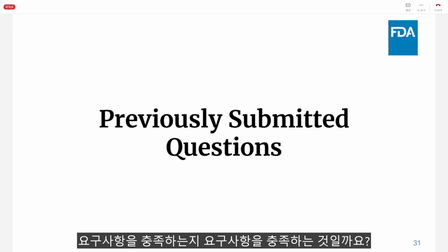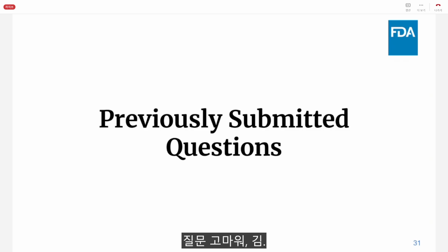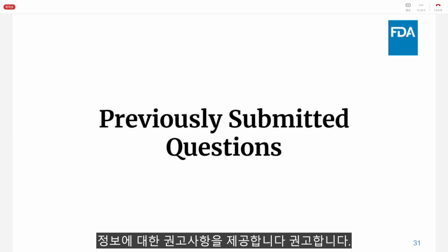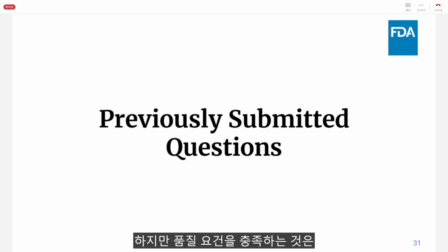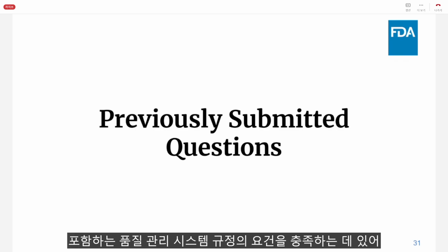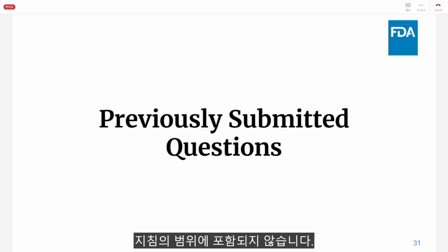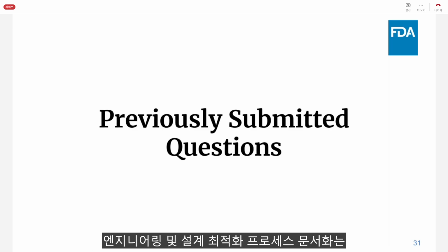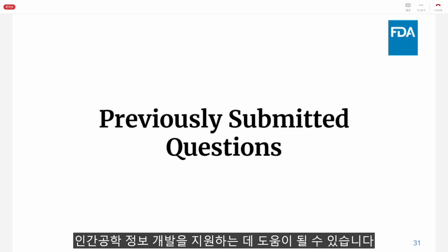Thanks for the question, Kim. The HF content guidance provides recommendations on what human factors information to include in marketing submissions to CDRH. However, fulfilling the requirements for the Quality Management System Regulation, which incorporates the 2016 edition of ISO 13485 by reference, is not within the scope of this guidance. A manufacturer's internal documentation of risk management, human factors engineering, and design optimization processes can help support the development of the human factors information described in the human factors content guidance.